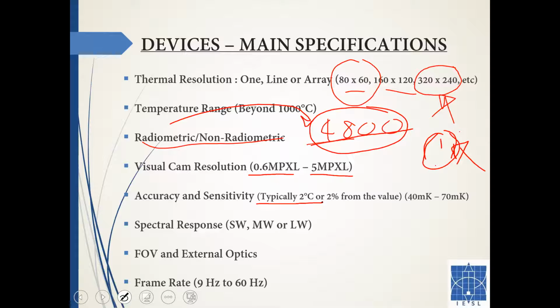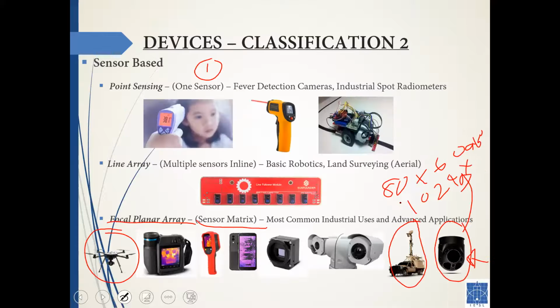These industrial maintenance imagers typically carry a 2-degree plus or minus error, or 2% of the value being measured, which is useless when it comes to temperature screening, right? But these point sensing devices have around 0.4 Celsius degrees accuracy, which is better than this, right? It's about the application. You are trying to measure temperature. Your error can be the difference between a COVID patient and who's not.